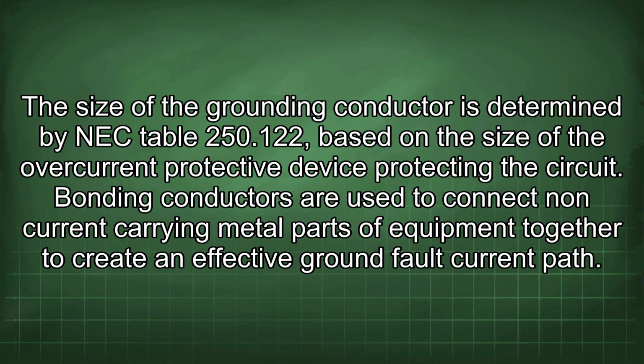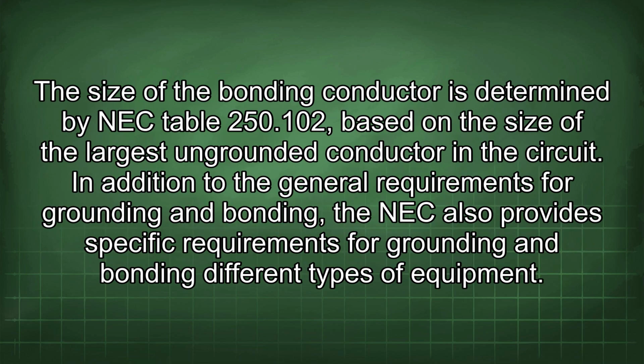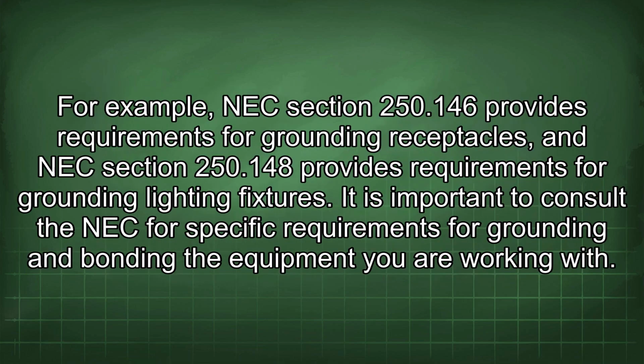Bonding conductors are used to connect non-current carrying metal parts of equipment together to create an effective ground fault current path. The size of the bonding conductor is determined by NEC Table 250.102 based on the size of the largest ungrounded conductor in the circuit. In addition to the general requirements for grounding and bonding, the NEC also provides specific requirements for grounding and bonding different types of equipment. For example, NEC Section 250.146 provides requirements for grounding receptacles, and NEC Section 250.148 provides requirements for grounding lighting fixtures.